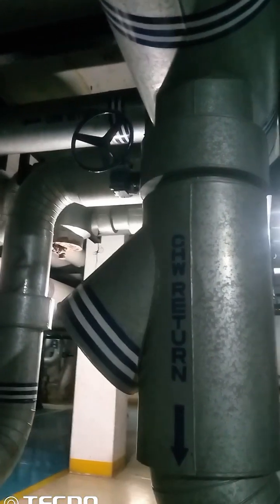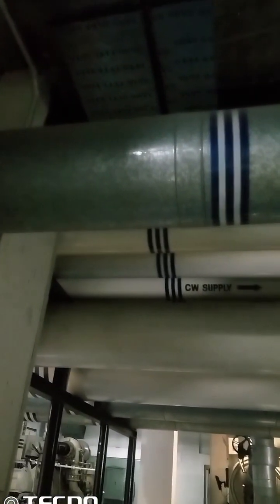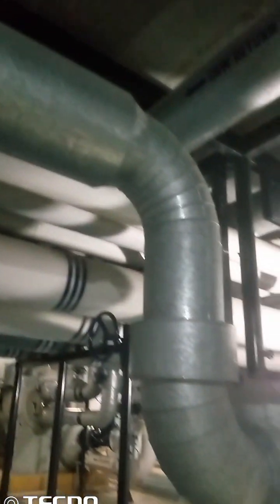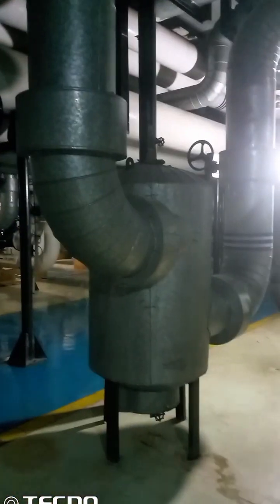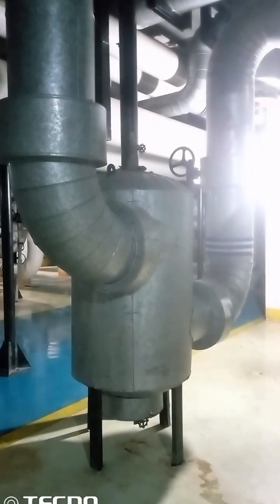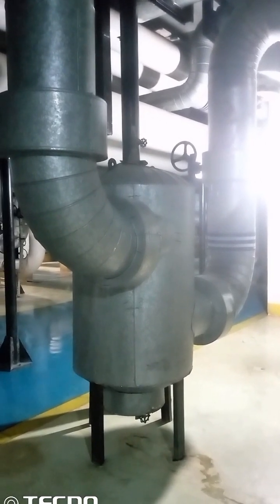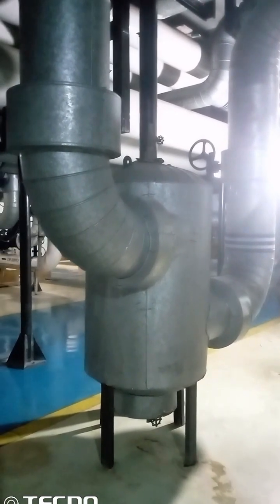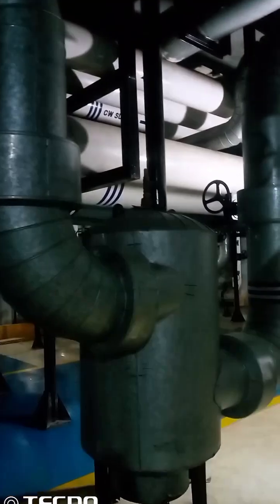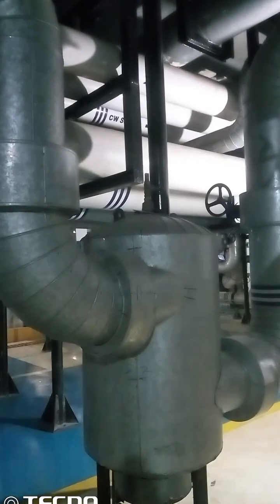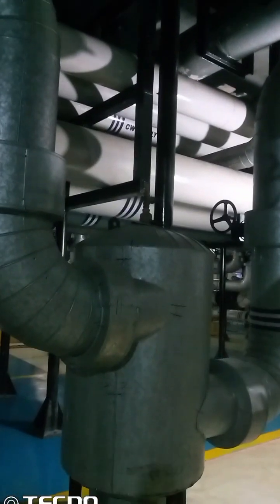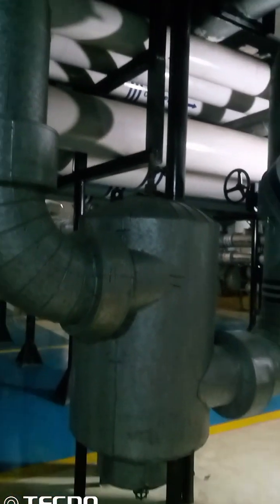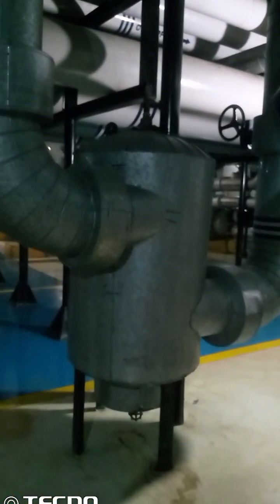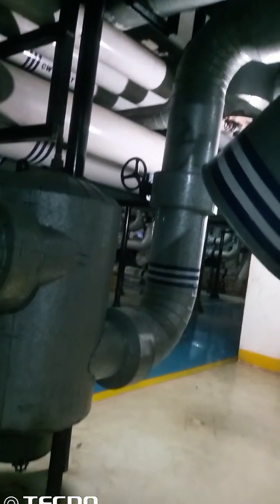And one thing more I want to add over here is the air separator. It is installed before the pump, and the main purpose of the air separator before the pump is that it stops air from entering the pump. And what are the consequences? If air is trapped or enters the pump side, the formation of bubbles or trapped air in the pump may affect the efficiency. So to stop this, to overcome that issue or problem, we use the air separator.